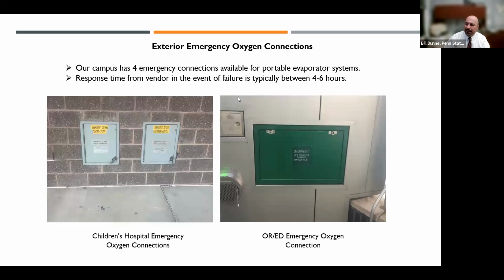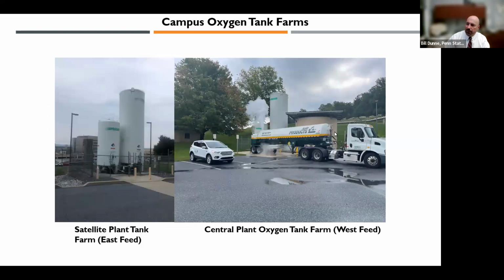Here are some slides of what our tank farms look like. The product comes in as a liquid from one of our distributors. We refill the primary and secondary tanks, and then it goes through a system that converts it from a liquid to a gas. Once it's in gas form, it feeds under pressure into the piping system at these two different locations, pressurizing the pipes into the hospital itself.